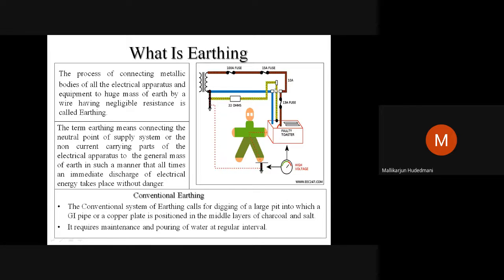Then the human body is in contact with the enclosure of the toaster. You can see the leakage current is flowing through the earth wire as well as through the body of the human operating. Now this earth wire is perfectly connected, so we will not see any current rushing down to the human body. It would have been taken perfectly over here.